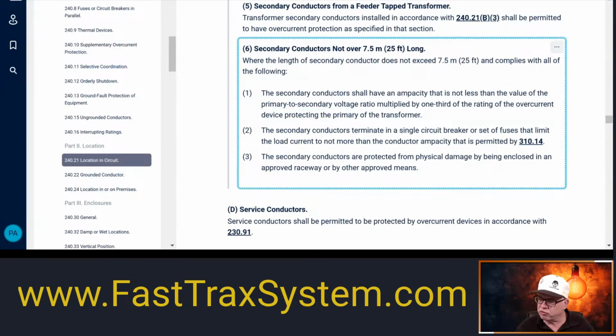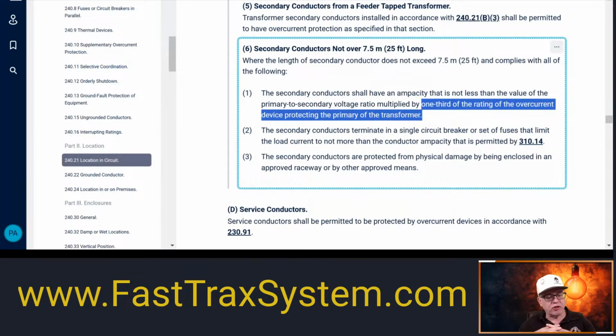And then it tells you to multiply that ratio by one-third the rating of the overcurrent protective device protecting the primary of the transformer. So let's say we had 125 amp primary protection. Let's just say that's what we had, and that's what we would have with a typical 75 kVA transformer, protecting the primary side. We're just going to do everything at 125. So in that scenario, we have to take one-third of that overcurrent protective device. Just throwing numbers out here, 125 divided by 3 is 41.66.